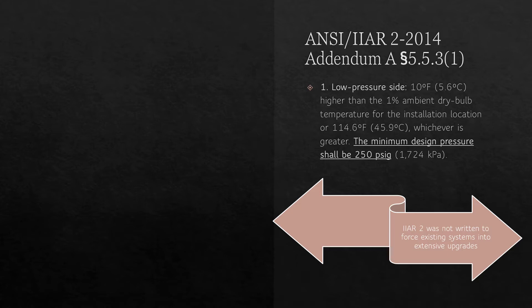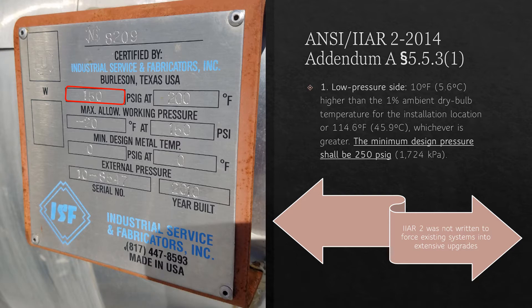For example, the 2014 version of IIAR Standard 2 increased the minimum allowable design pressure of the low side of a system to 250 PSI. However, many systems designed prior to that date utilized low side components that were designed for 150 PSI. While it was never IIAR's intent that Standard 2 be used to forcibly require extensive upgrades to existing systems, many such instances have occurred.